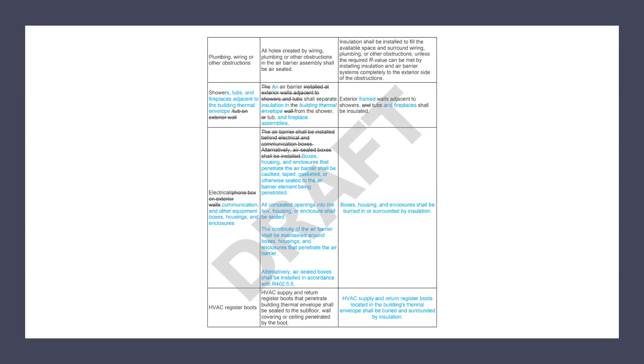They should not have metal boxes being exposed to attics that are not insulated. The older boxes used to have insulation on the inside of them, but those were not meeting the requirement for duct insulation. They were probably an R3 duct board on the inside of them. Those cause a lot of condensation, a lot of mold issues. So really you need to have the insulation on the outside, not the inside of the boots. But I still see them used from time to time. So that's a lot of changes that happen with that part of it.